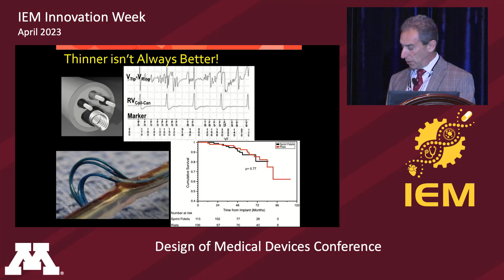And shocks are great if you need a life-saving shock. Shocks aren't so great if you're just sitting around doing nothing. And people don't like getting shocked when they're not supposed to. And it hurts, and it can lead to other arrhythmias. And in this thinner lead, there really wasn't enough support around the conductors, and the conductor cables extruded out through the insulation. So both of these are sort of different problems leading to lead failure, and they both had a survival rate of about 70% when you get out to 5 or 6 years, about a 30% lead failure, and they were comparable when they were compared.